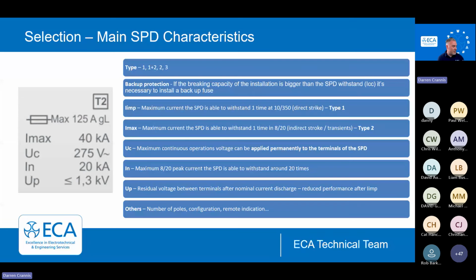The next on there, we can see it says max 125 amp gL. That's its backup protection. And we try and go with the largest backup protection you can. So all that energy goes through that circuit breaker down the SPD. You don't really want the circuit breaker to destruct or to disconnect. A lot of these now, especially in domestic, you'll see they're rated at 125 or 100 amp. They can literally sit on the bus bar and they let the distributors use as backup protection. But be aware that when you're building larger panels or you've got larger installations, these might be 63, 32, or the largest frame size you can, and the manufacturer will state if it's fuses or electronic devices you can use. So that's really important.